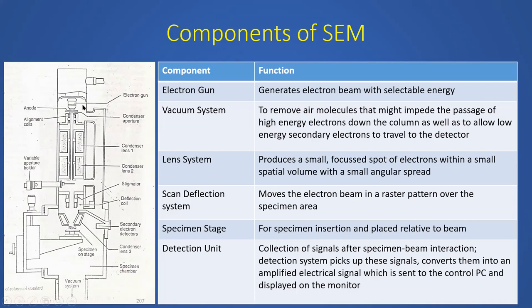And then you have your vacuum system. You need a very good vacuum system so that the electrons can travel through the column and interact with the specimen, because electrons can't travel in air. So you remove the air molecules that might impede the passage of these high energy electrons down the column, as well as to allow low energy secondary electrons to travel to the detector. That's the need for the vacuum system.